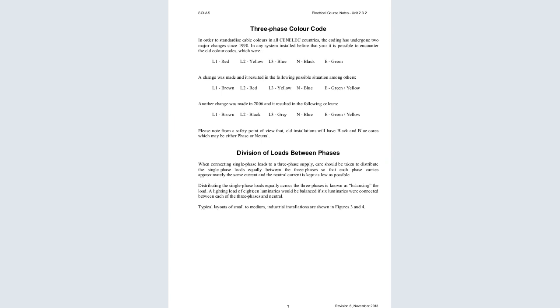But other countries have changed, and they're using line 1 being brown, line 2 being red, line 3 being yellow, and the neutral being blue, and then E being the earth. Another change was made in 2006 for other countries still: line 1 being brown, line 2 being black, line 3 being grey, the neutral being blue, and the earth being green stroke yellow.